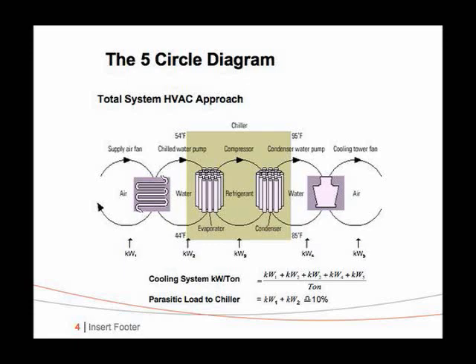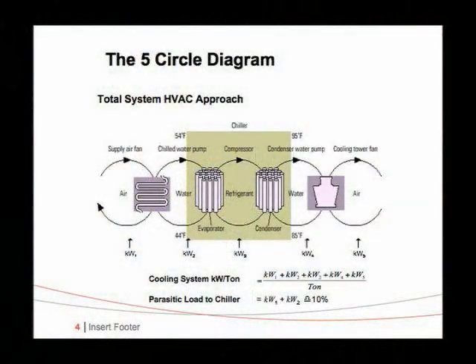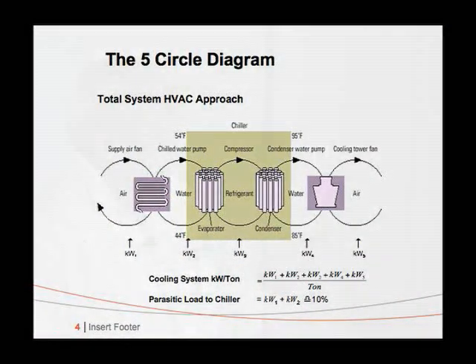Anybody want to give a shot at what's the best kilowatt per ton for air conditioning applications in the tropics? 1985, AT&T factory in Singapore making phones. 0.7 kilowatt per ton, which is a sum of all kilowatts. And presently, as TRANE, we are offering on the water side. Water side means from here to the end. No air side. Water side at 0.6, typically, although we've offered 0.58.